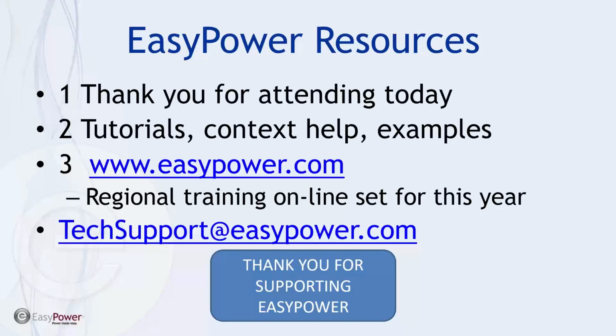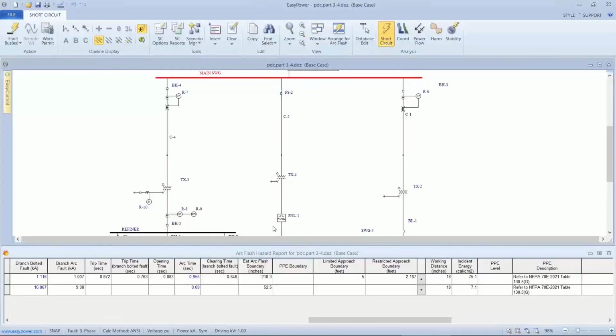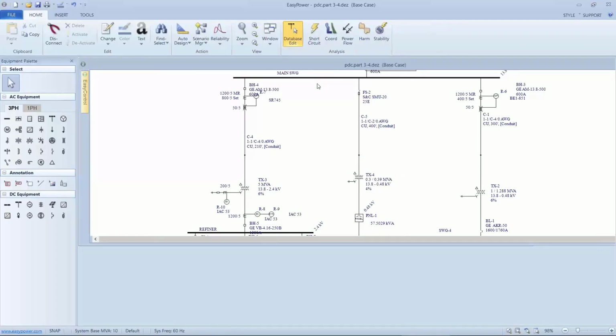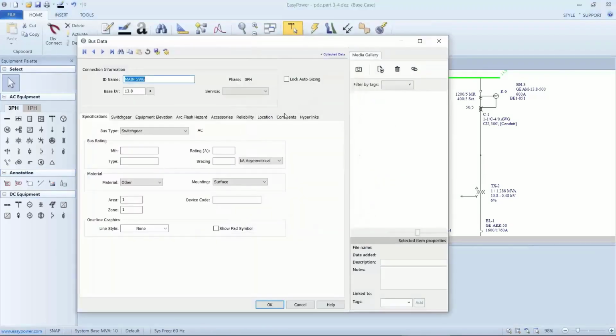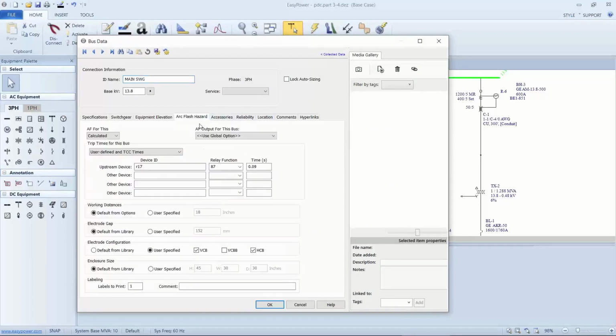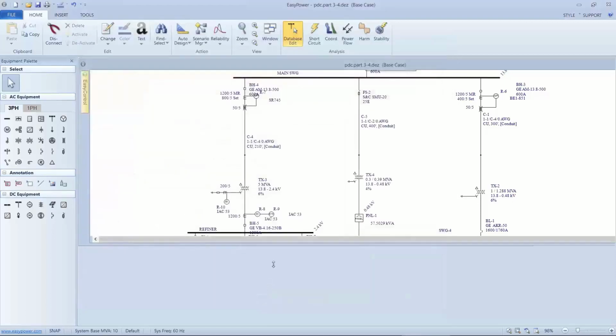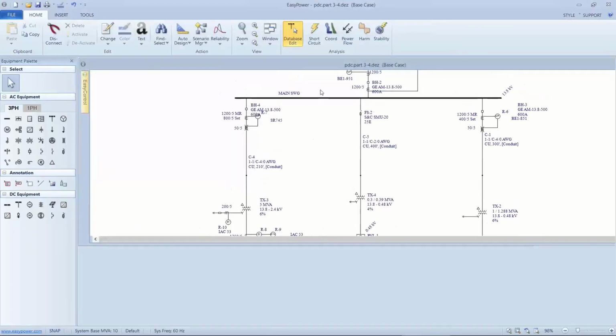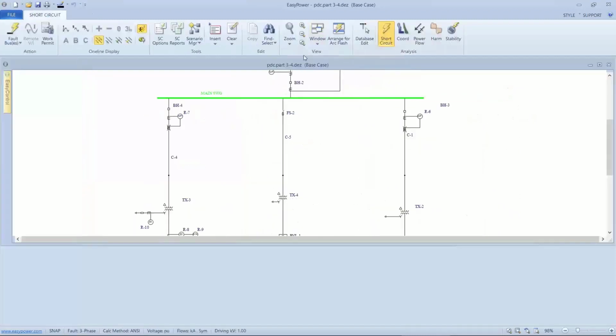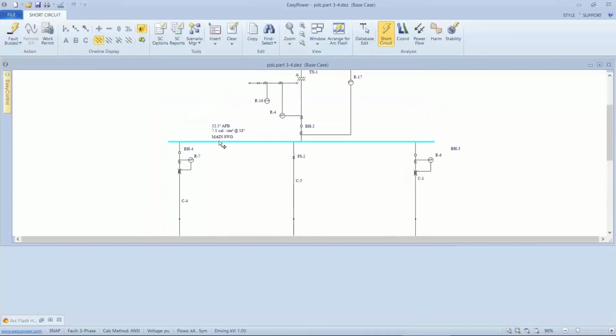Now, there was one question from Navin. The bus, you can control what's indicated on the bus. In that one example I was showing, if I want my differential relay to be the only thing that shows up for calculations, I'd have user-defined time. And then when I go to calculate this downstream bus, it will only show that. My incident energy will reflect that calculation. Thanks for the question.